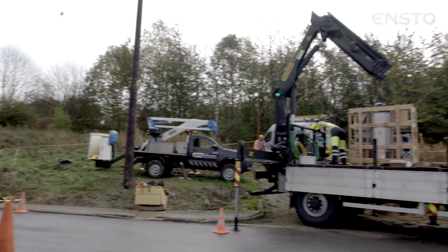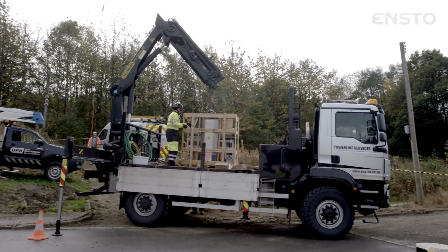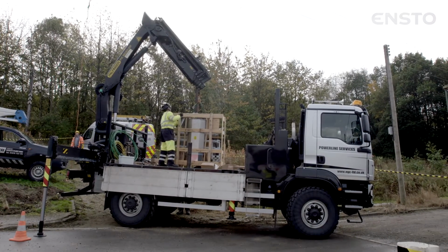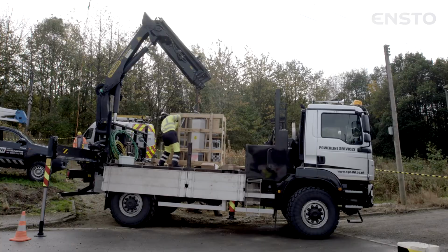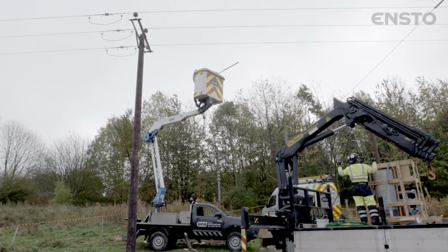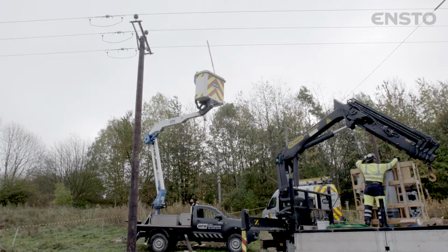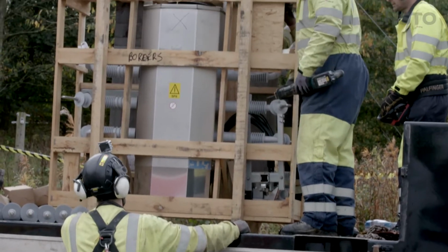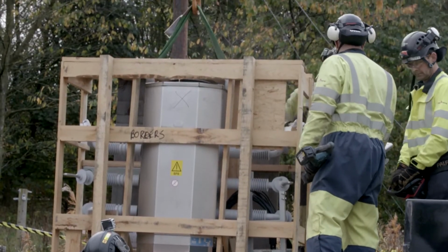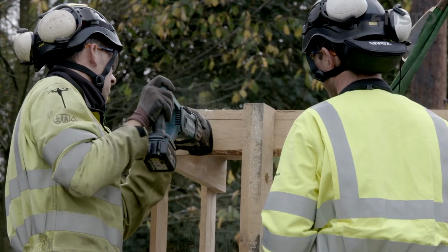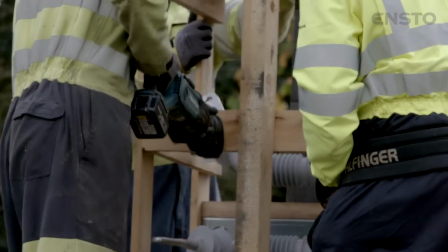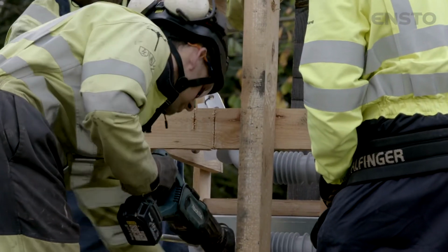The Ensto switch will arrive in a 2-layer wooden crate. Take care of the insulator bushings, which are fragile. Do not attempt to lift or manhandle the switch by the insulator bushings. Take care of the switch operating shaft, which protrudes from the bottom of the switch and is protected by the inner crate. The switch must not be rested upon the switch operating shaft.